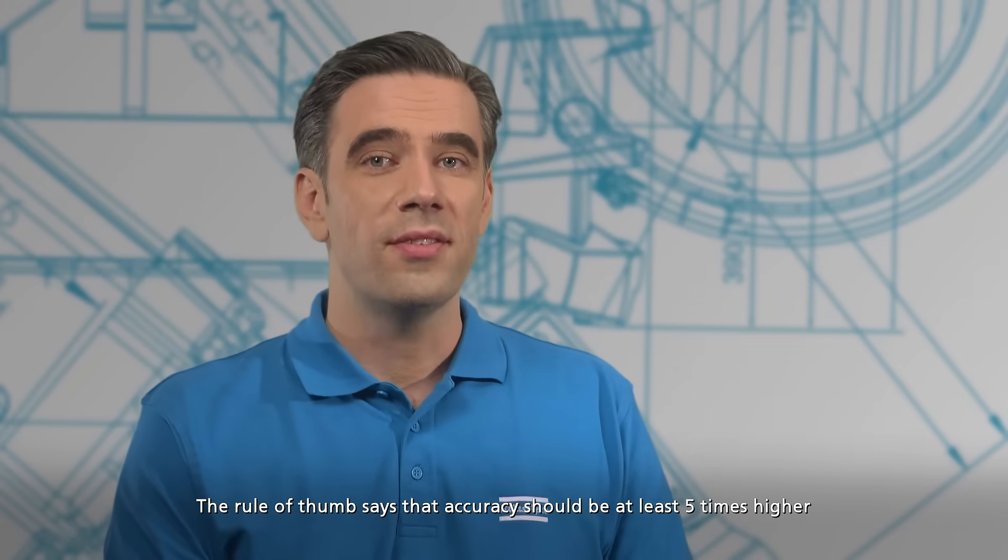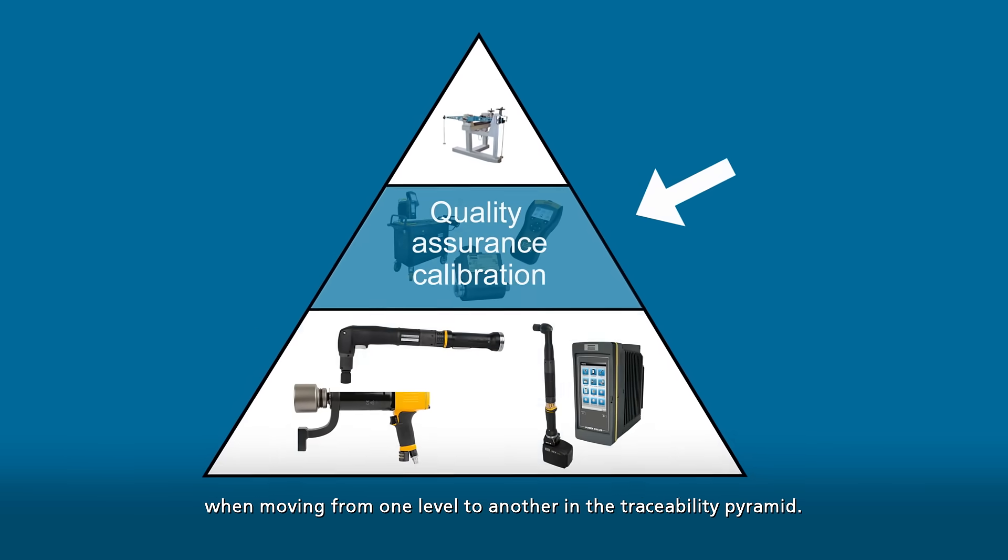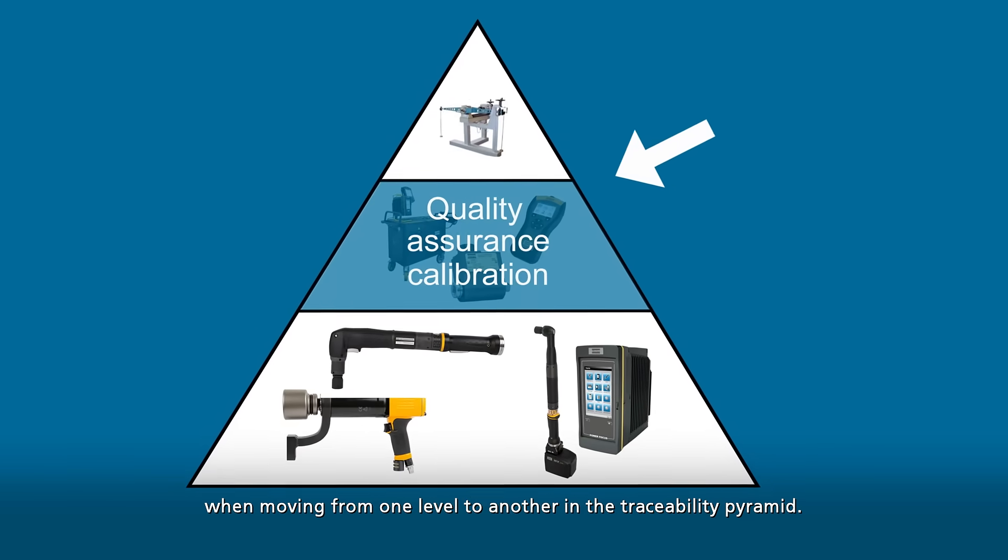The rule of thumb says that accuracy should be at least 5 times higher when moving from one level to another in the traceability pyramid.